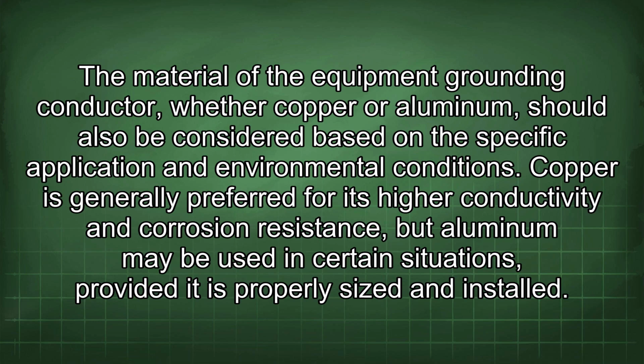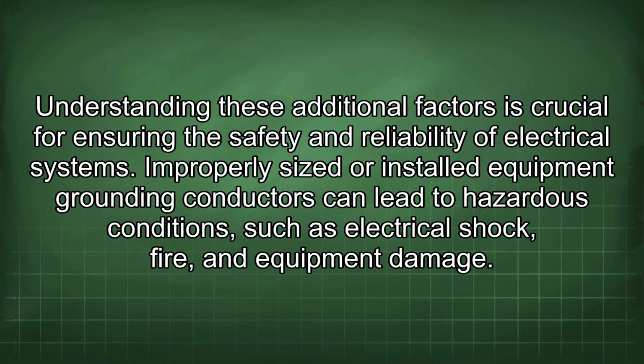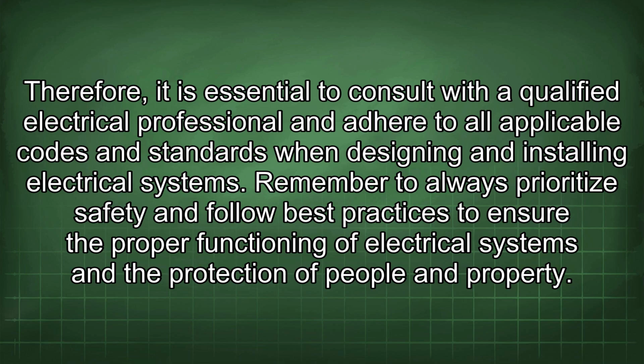The material of the equipment grounding conductor, whether copper or aluminum, should also be considered based on the specific application and environmental conditions. Copper is generally preferred for its higher conductivity and corrosion resistance, but aluminum may be used in certain situations provided it is properly sized and installed. Understanding these additional factors is crucial for ensuring the safety and reliability of electrical systems. Improperly sized or installed equipment grounding conductors can lead to hazardous conditions such as electrical shock, fire, and equipment damage. Therefore, it is essential to consult with a qualified electrical professional and adhere to all applicable codes and standards when designing and installing electrical systems. Remember to always prioritize safety and follow best practices to ensure the proper functioning of electrical systems and the protection of people and property.